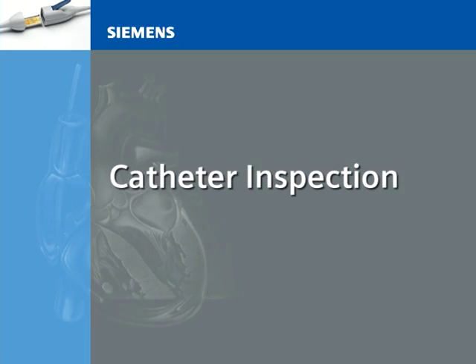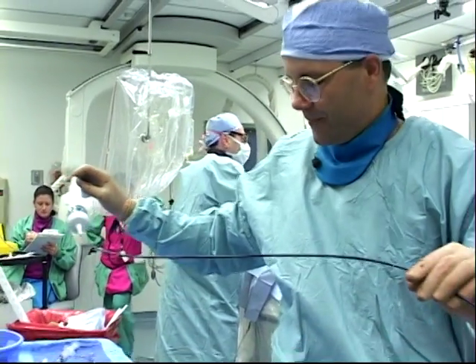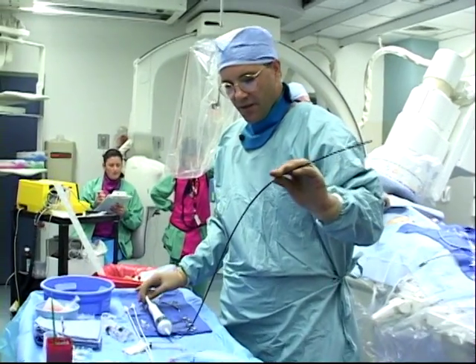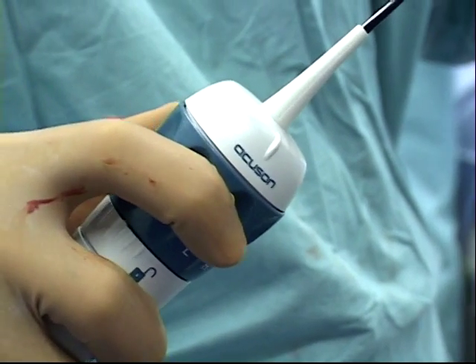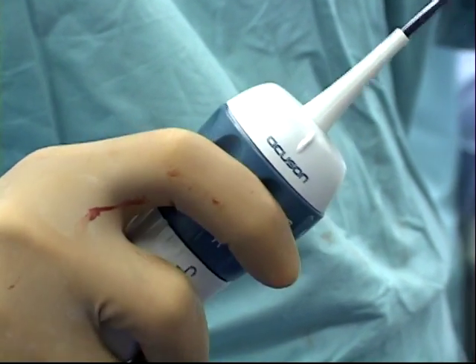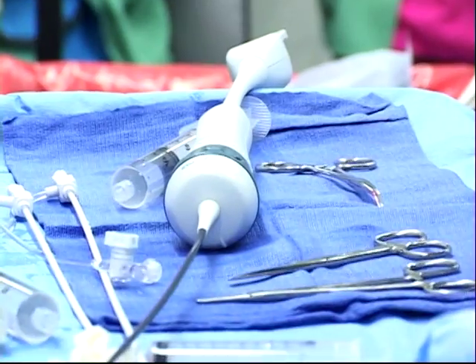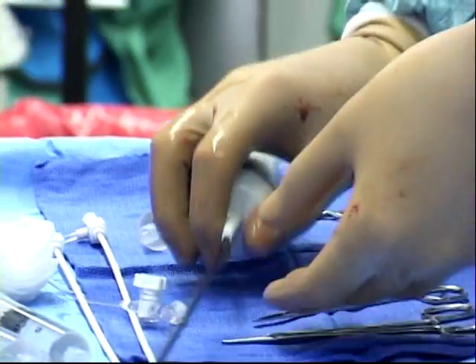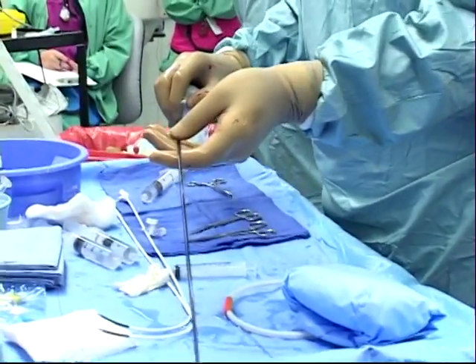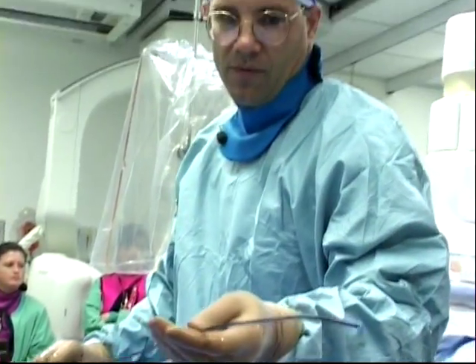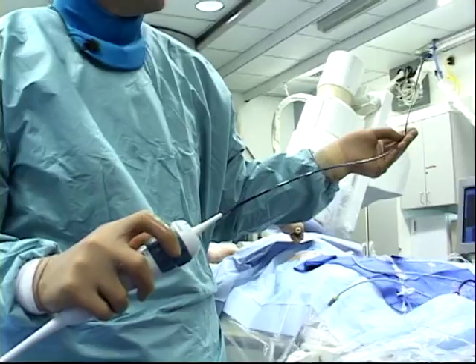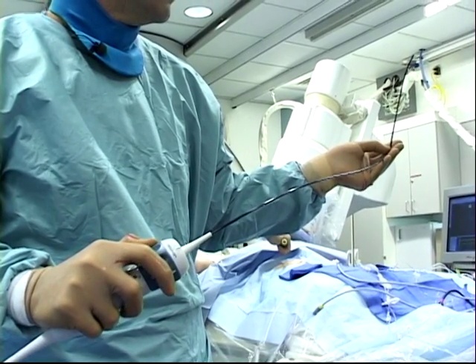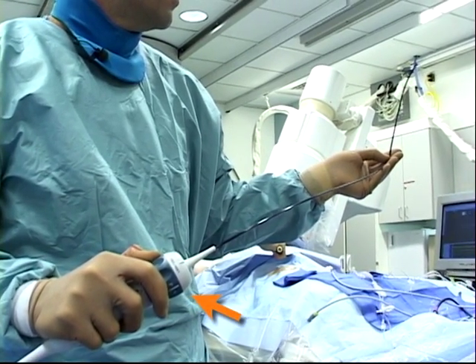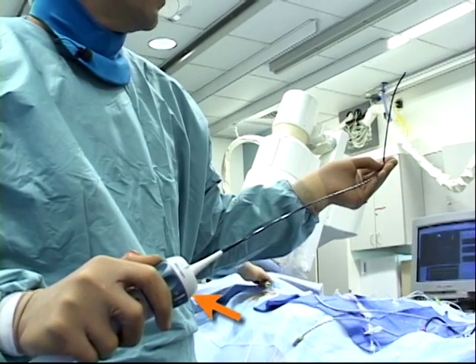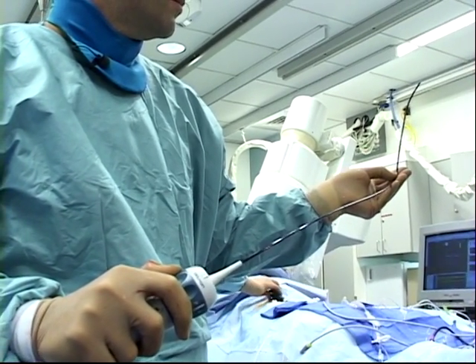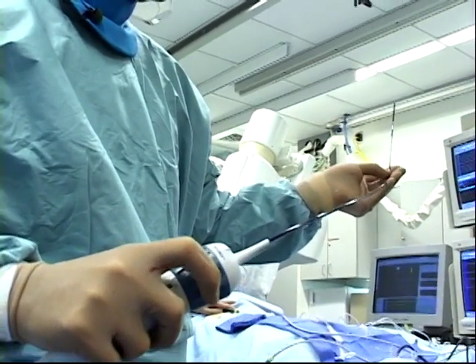Catheter inspection. Before using the AcuNav catheter, visually inspect the catheter and evaluate the performance of the steering and tension control knobs. Using sterile technique, run your gloved fingers along the entire surface of the catheter, inspecting for any signs of mechanical damage. Hold the catheter body in one hand and turn the posterior-anterior steering knob clockwise to steer the tip in the anterior direction. Then turn it counterclockwise to steer it in the posterior direction.